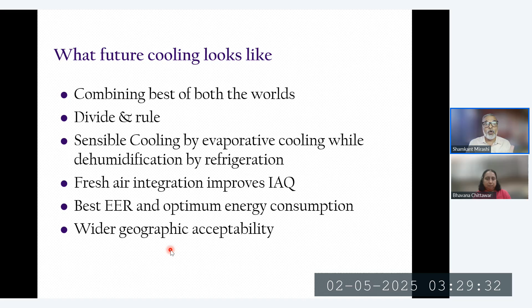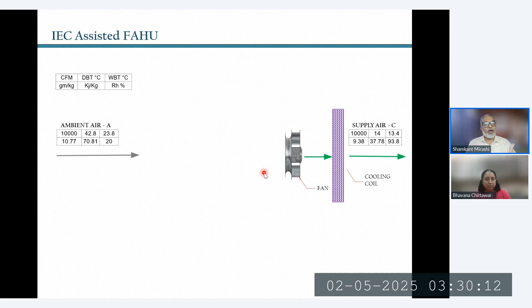I have the same fresh air. We discuss applications like pharma, chemical and food, where these kinds of requirements exist, where you take the fresh air, cool it down by a refrigeration coil, and offer it in the space. Even your standard commercial buildings have these systems called TFA, treated fresh air systems, or fresh air systems. They take fresh air, put it on the coil, and take the air to a very low temperature, right? And these are loads which are almost 3 times those of regular air conditioning. We are saying that since we have a technology which can pre-cool that air at very low power penalty, we intervene there as well.